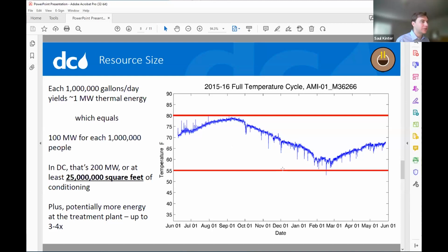Based on this, we conservatively estimated we could put a 10 degree Fahrenheit delta T on the source system. If you do the math, that means for every million gallons per day of flow, you have about a megawatt of thermal energy. We have close to 300 MGD of flow, but in terms of base flow overnight, we figured we could access maybe 200, meaning maybe 200 megawatts of thermal energy - enough to heat and cool maybe 5 to 10% of the buildings in DC.